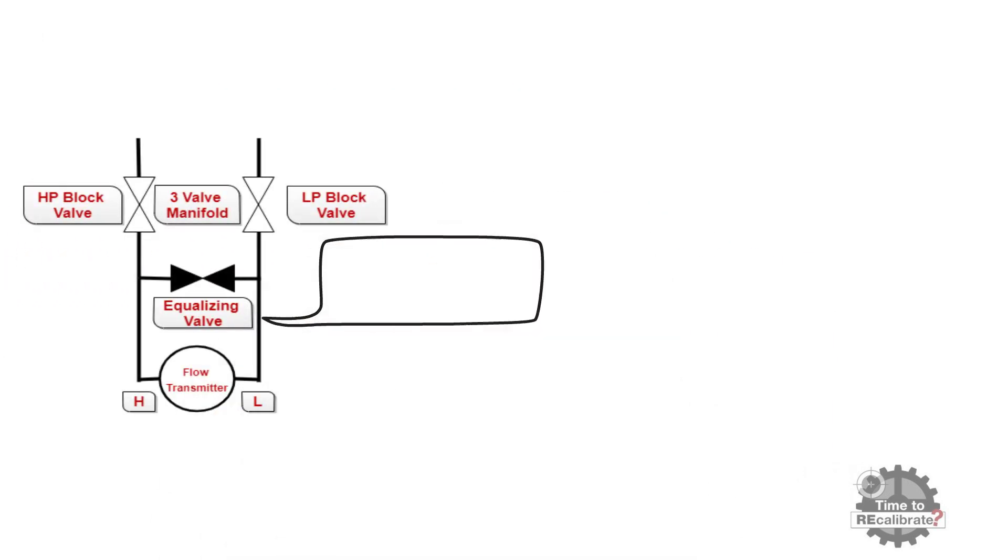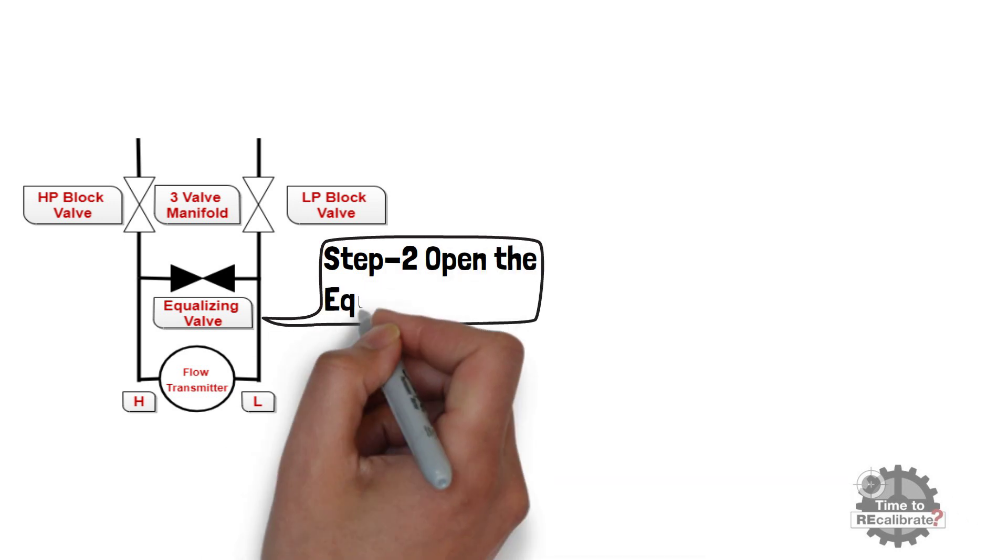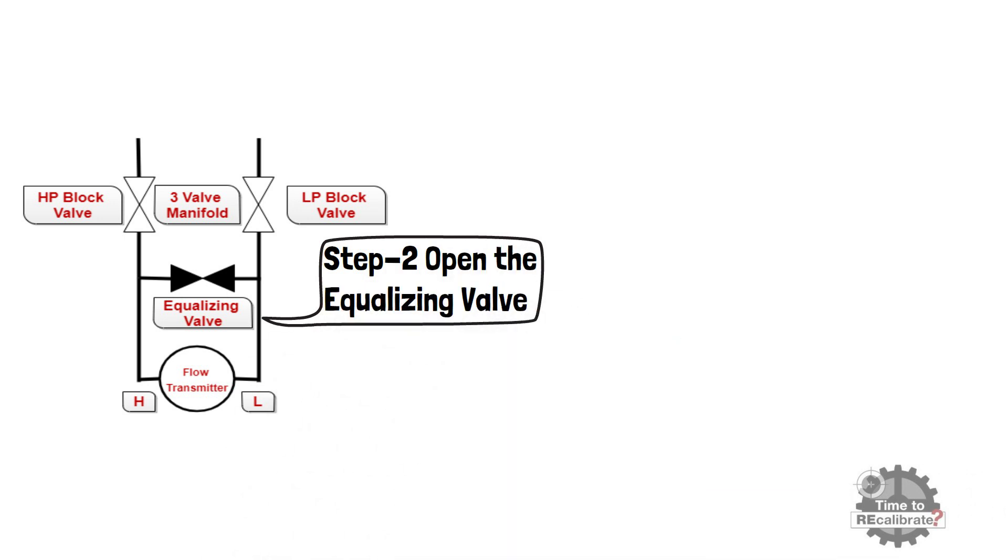In second step, open the equalizing valve by rotating valve in counterclockwise direction. This will balance the pressure to both the high and low sides of the transmitter.